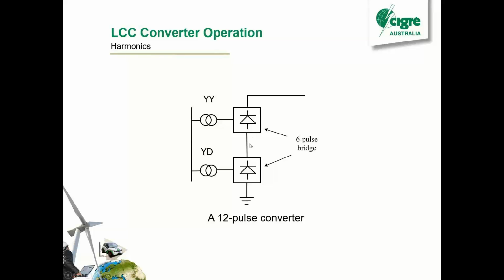So you can't just have 2 6-pulse bridges connected with the same vector group on your transformers, because then you'd just add up. You'd still have the same 6-pulse profile if you did that. You need to introduce a 30-degree phase shift between the 2 bridges. And you just do that with a delta connection. So on all 12-pulse converters, you'll have one bridge star connected and one delta connected, so you can get your 30-degree phase shift to offset the converters.